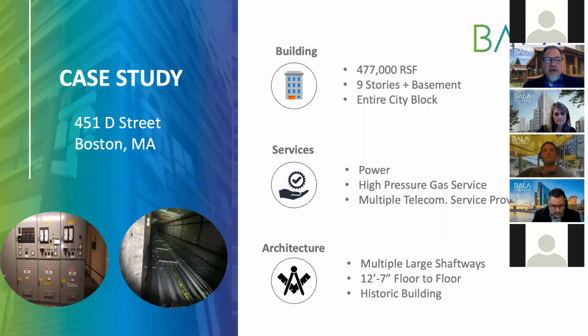But it has 13.8 kV electrical service, 3 4,000 amp, 480 volt double-ended substations. It has 40 watts a square foot. So if you remember from the matrix, this meets the metrics. The power meets the metrics. This one's an easy home run. It's just going to be tight floor to floor. What we did to this is we added 2 300-ton gas-fired DX rooftop units that were custom units for makeup air. And then we provided a Strobic fan array, which we'll show you a picture of, for our exhaust. Did a glycol heat recovery system between the supply and the exhaust air for energy recovery. And we also utilized 2 abandoned elevators for shafts for not only power and communication, but our exhaust and our water risers, and so forth.